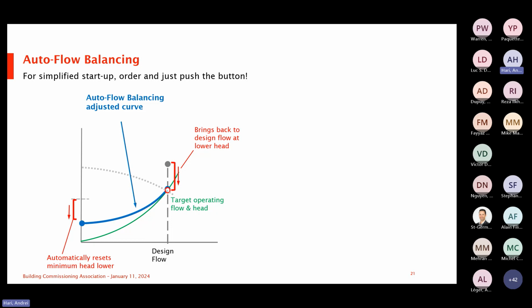That's all it is. And it's funny you ask that, because that's one of the fundamental challenges in understanding how systems work: typically, a lot of what we do today is still based on pressure control. So we have valves that open or close, and those valves opening or closing adjust the pressure in the system. That pressure change is then dictated in terms of increasing or decreasing your flow requirements. Like if I've got a fan coil and I'm closing off a valve, I'm closing that valve because I need less flow. And I'm opening that valve because I need more flow. When I open that valve to increase flow, I'm starting to move more water through that fan coil. If I'm moving more water through that fan coil, the resistance in my system starts to increase.